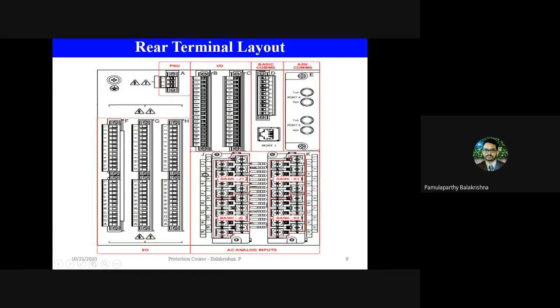For example, for communications, you have basic communications like RJ45, which we have in laptops, or you can have advanced fiber optic communication. If you don't need advanced fiber optic communication, you can just remove this card. Like that, it can take either DC supply or AC supply. It can run with any of the supply types. So it is designed in a very flexible and modular manner, such that it caters to any application related to any machine in the power system or in the substation.